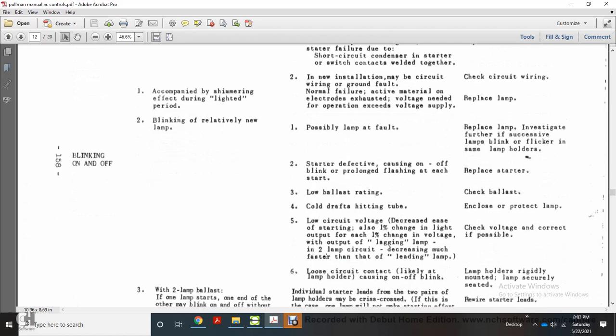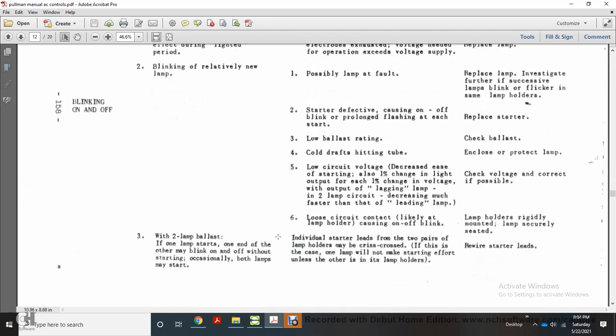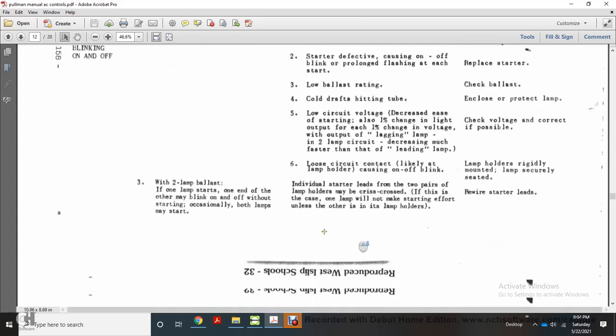Corrective actions: check circuit wiring; replace lamp. For blinking on and off: replace lamp and investigate further. For starter effects causing blinking, replace starter. For low ballast rating, check ballast. Correct cold drafts and protect lamp. Low circuit voltage decreases ease of starting; a one-percent change in voltage causes one-percent change in light output. Lagging lamp circuits decrease much faster than leading lamp circuits; check and correct voltage if possible. For loose circuit connections at lamp holders causing on-and-off blinking, ensure lamp holders are rigidly mounted and lamps are securely seated. For two-lamp ballast blinking where one lamp starts and the other blinks without starting, check that individual starter leads for the two pairs of lamp holders are not crisscrossed; if so, rewire starter leads.